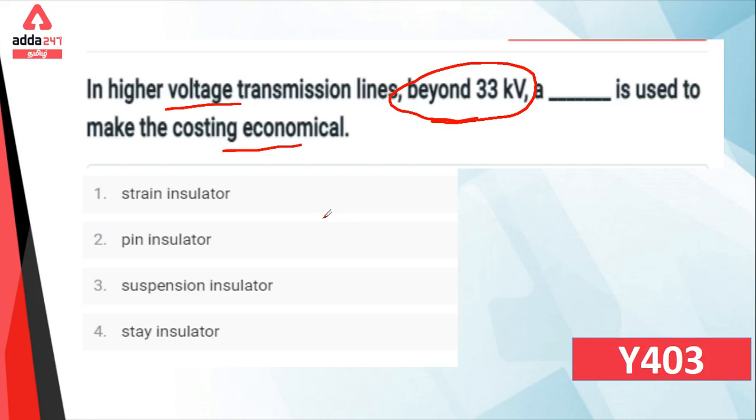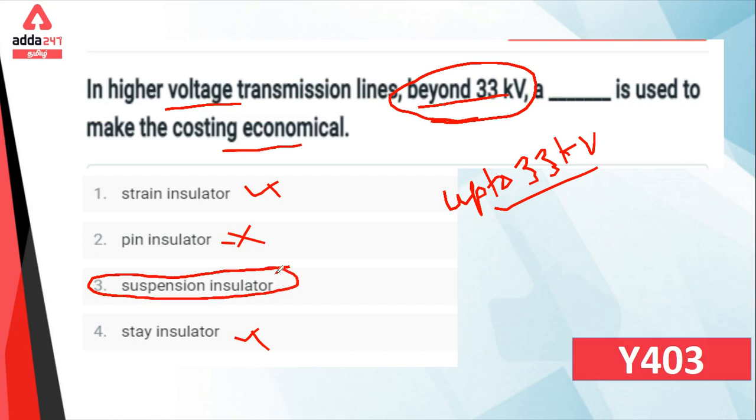For high voltage transmission lines, strain insulator and stay insulator are the same. Pin insulator is used up to 33kV. For beyond 33kV, above 33kV, we use suspension type insulator. For economic reasons, we use pin type up to 33kV, and suspension type for higher voltages. The answer is suspension type insulator.